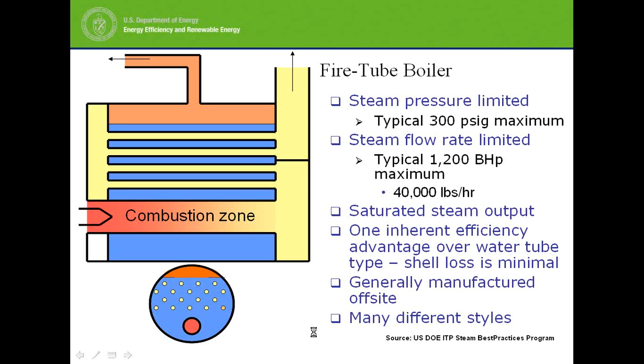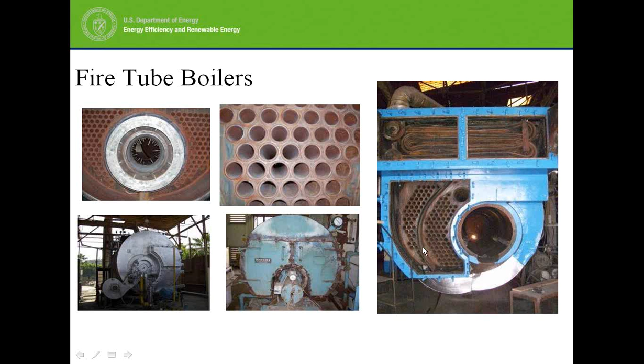Some quick pictures, if you ever had a chance to open and look at them. The fire tubes, so basically our combustion gases, our flue gas, are in the tubes, and you've got the main burner tube, which is the radiation section, followed by the convective sections and multi-passes, and so on and so forth.